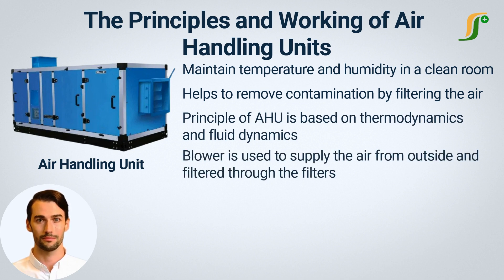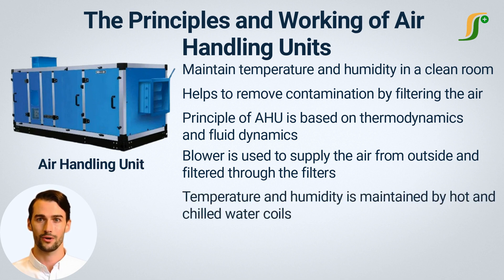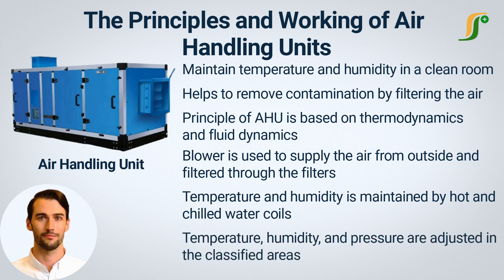A blower is used to supply air from outside and filter it through filters to remove contamination. The air is then cooled or heated as per the required temperature before flowing to the clean room area. This is done by the hot and chilled water coils present inside the air handling unit. Temperature, humidity, and pressure are adjusted in the classified areas by the air handling units. Air contamination is also removed by filtration, which helps maintain the clean area classes.